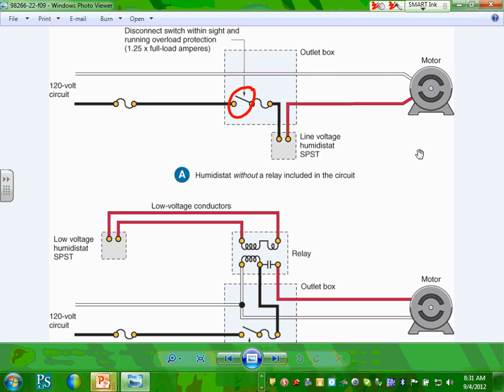Typically, they're built in right next to them, where you can have it on, off, and you can adjust the temperature. So that's basically built into the machine. Or you can have a thermostat, they call it a line thermostat. First it has to have a switch, and then it has to go to a line thermostat. So when the temperature goes high, it closes this and turns this fan on, right? When it goes lower than a certain value, it opens it and turns it off. So that's called line control.